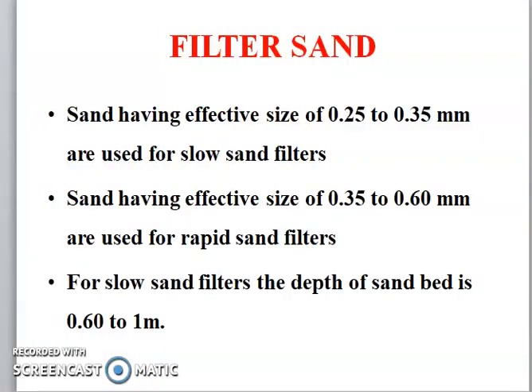Filter sand having an effective size of 0.25 to 0.35 mm is used for slow sand filters. For slow sand filters, the depth of the sand bed is 0.60 to 1 meter.